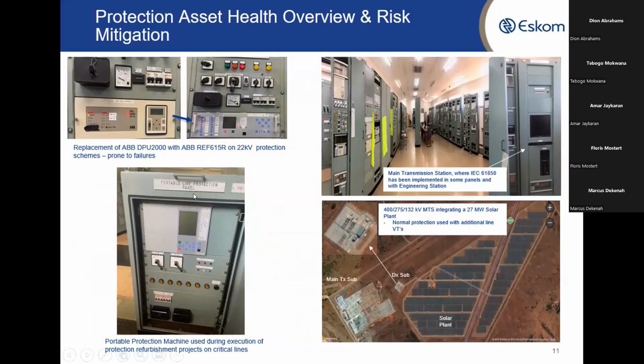portable line protection schemes, which we call washing machines, where we implement projects on critical lines, or where the protection may have failed on a feeder. We can use this protection scheme as a temporary measure to keep the line in service. In the future, if you look on the right, we have at a new transmission station, as we implement these projects, where IEC 61850 has been implemented, we also include engineering stations so that when settings are implemented, or if you want to do the relay downloads, you don't necessarily have to connect through your laptop, but you can have all these engineering stations able to assist you in that regard.